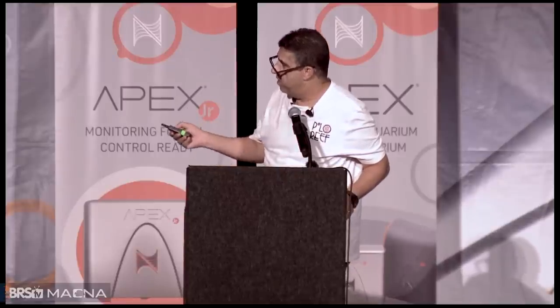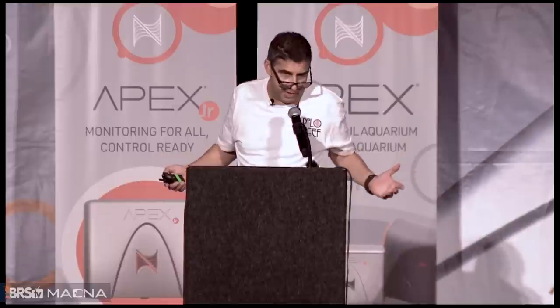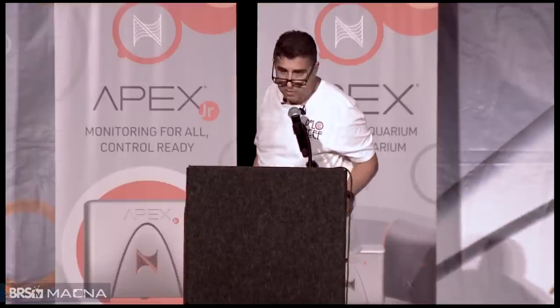Having 4 5-ton units also separates the risk. These things need Freon and servicing. One goes down, we just turn the other one on. It actually does it automatically. So the split, there's 4 of these things, and they are split up in the system, so we can run 2, 3, and there's extra spares around all the time.